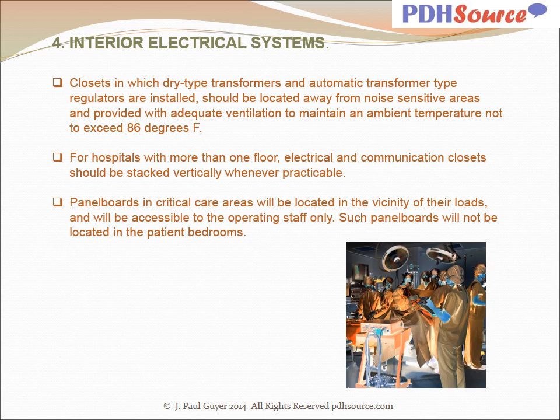Closets in which dry type transformers and automatic transformer type regulators are installed should be located away from noise sensitive areas and provided with adequate ventilation to maintain an ambient temperature not to exceed 86 degrees Fahrenheit. For hospitals with more than one floor, electrical and communication closets should be stacked vertically whenever practicable. Panel boards in critical care areas will be located in the vicinity of their loads and will be accessible to the operating staff only. Such panel boards will not be located in the patient bedrooms.